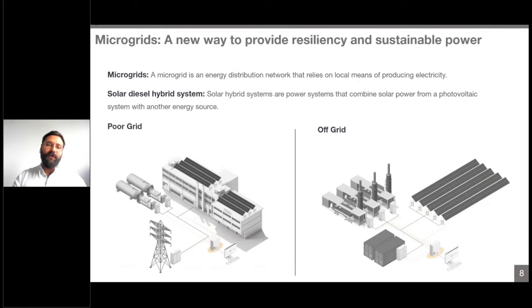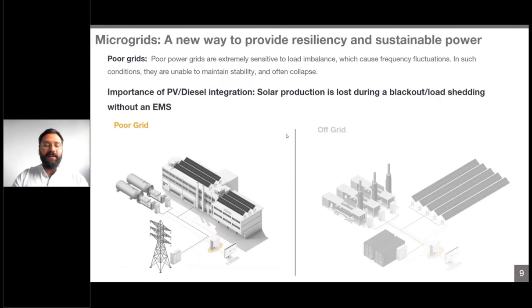So to go to some concepts, as you probably know, the microgrid is an energy distribution network that consists of several energy sources. The solar diesel hybrid system is a type of microgrid where the PV is the main source, integrated with several sources like utility, gensets, and BSS. I'll be differentiating today between two main configurations, the poor grid and the off-grid systems. The poor grid is mainly used in countries where the grid is not reliable, for example in Pakistan, and there is a diesel genset as a backup that is needed for these sites.